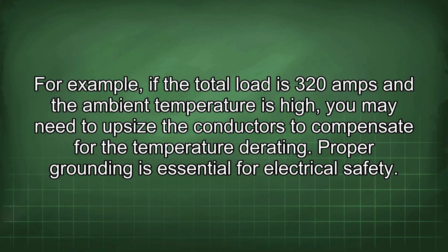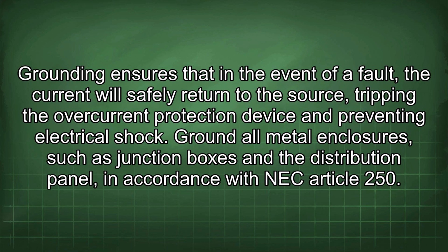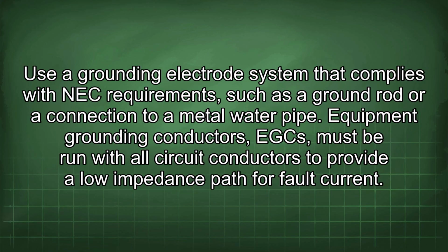Proper grounding is essential for electrical safety. Grounding ensures that in the event of a fault, the current will safely return to the source, tripping the overcurrent protection device and preventing electrical shock. Ground all metal enclosures, such as junction boxes and the distribution panel, in accordance with NEC Article 250. Use a grounding electrode system that complies with NEC requirements, such as a ground rod or connection to a metal water pipe. Equipment grounding conductors, EGCs, must be run with all circuit conductors to provide a low impedance path for fault current.